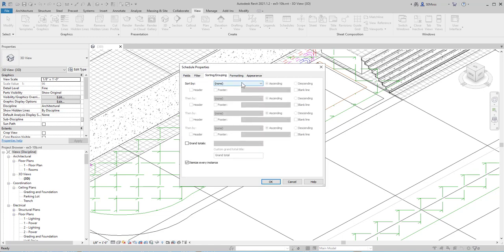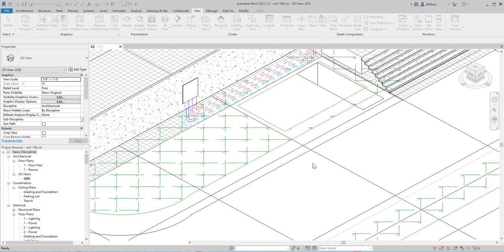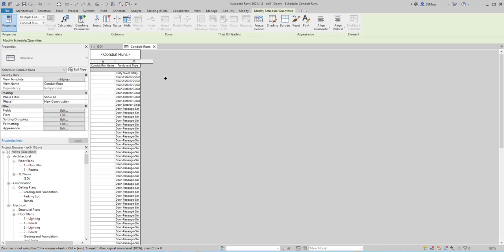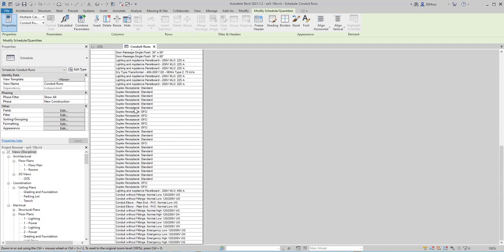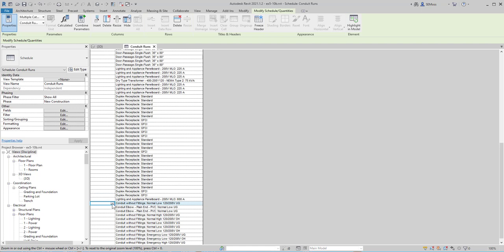Then I'm going to go to Sorting and Grouping and sort it by Conduit Run Name, then click OK. Obviously, doors aren't going to have a conduit run name, nor will the Utility Vault or Electrical Appliances. But notice that when I come to the bottom, here are some conduits that have not been assigned conduit run names. Luckily I've assigned types, so I can see what run name they should be under. I'll select Normal Low, and as soon as I assign it a conduit run name, it's going to disappear because it no longer meets that filter.